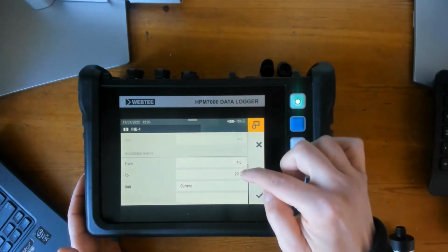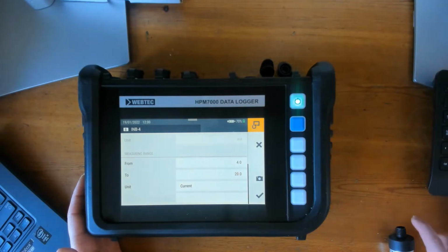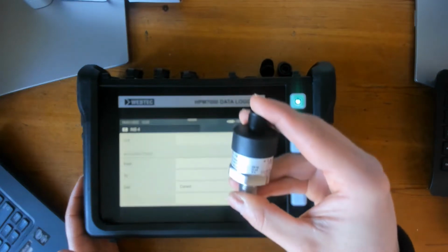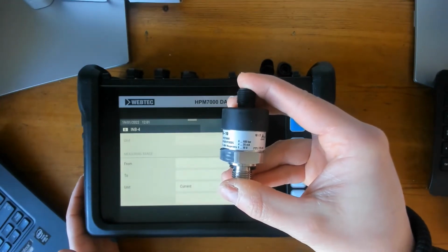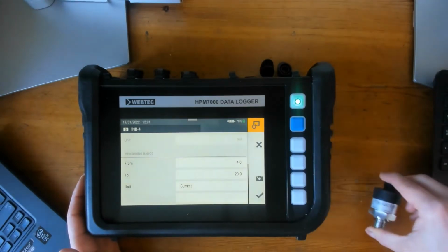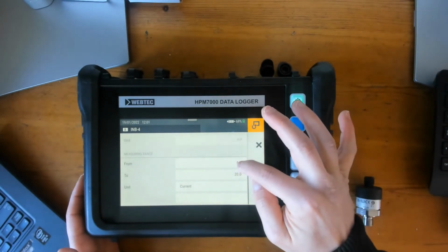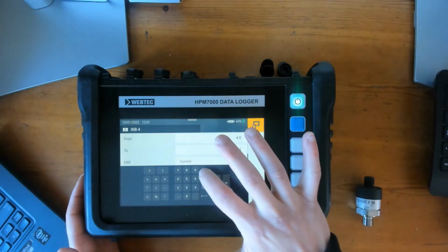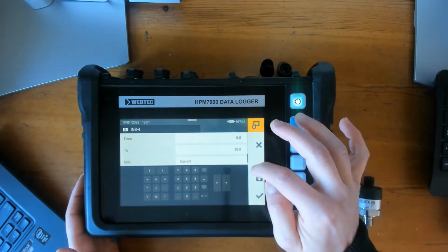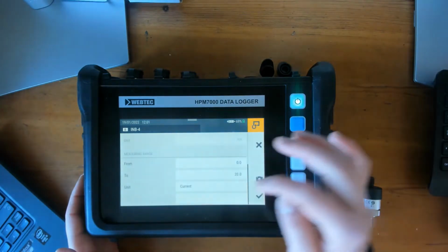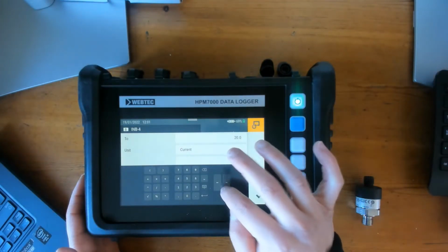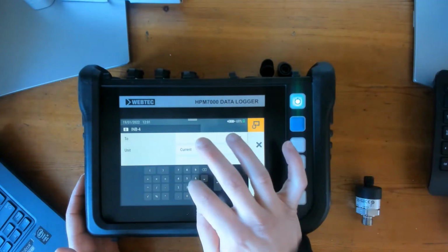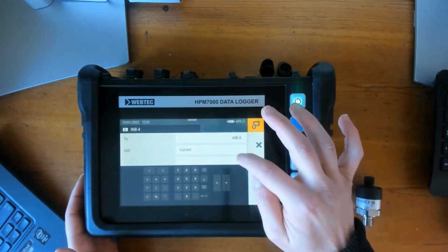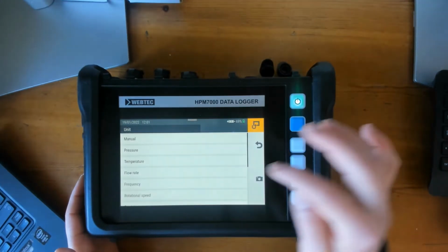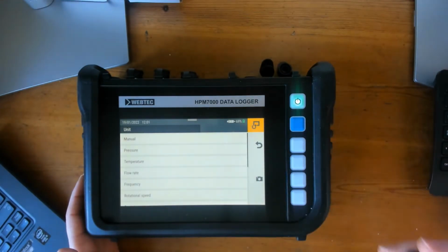And then we need to do the measuring range. So in this case, I'm connecting this 600 bar pressure transducer. So my measuring range is going to be from 0 to 600. And my units are going to be bar.